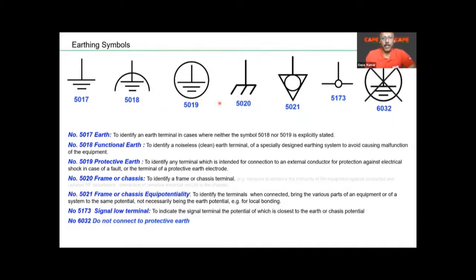5019 is safety earthing. 5020 is called chassis earthing. 5021 is called frame or chassis equipotentiality. 5173 is called a signal low terminal. So wherever a terminal is marked as 5173, you must understand that the potential of that particular terminal is very close to earth and is going to become the reference for the earthing. And 6032 is do not connect to a protective earth. So basically, earthing is done based on its requirement. First, you should understand these kinds of requirements.